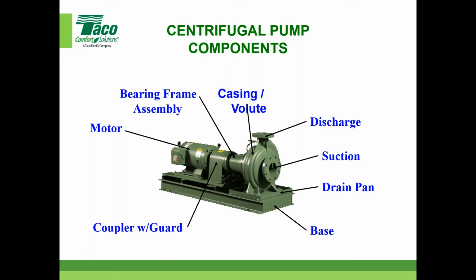Whether or not the unit needs to be physically isolated from the building with an inertia block and springs, that's a separate issue. That does not have anything to do with stiffening the base so that the pump is properly aligned, so that it doesn't come out of alignment. So isolating from the building, that's a separate discussion, and you should have that discussion with your acoustical engineer or vibration specialist that wants to minimize the amount of noise and vibration that's transmitted into the structure of the building.